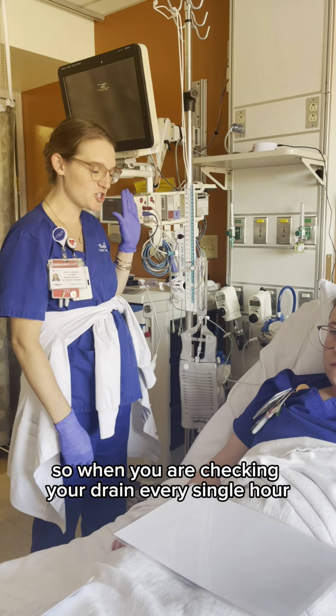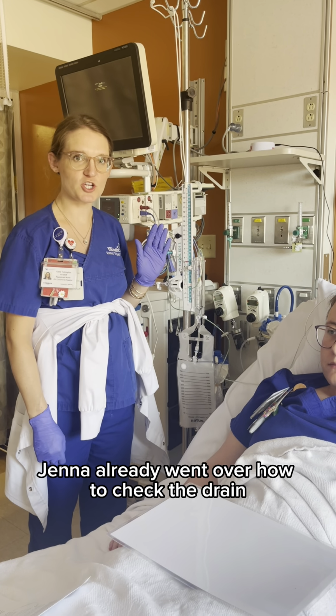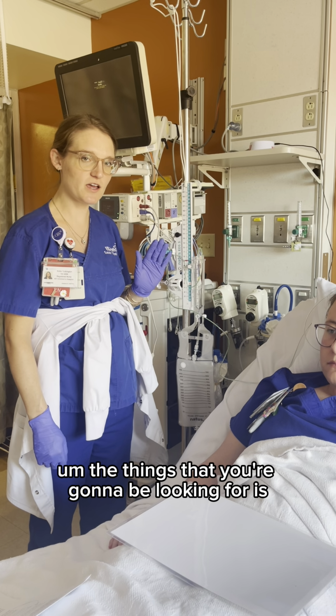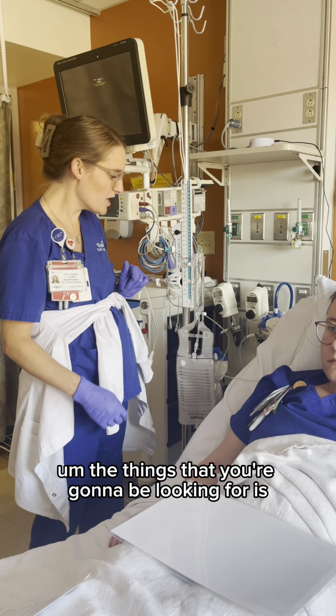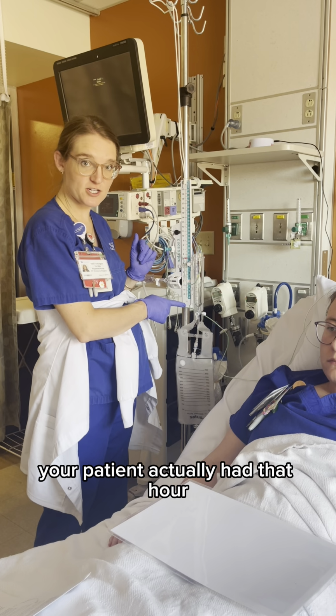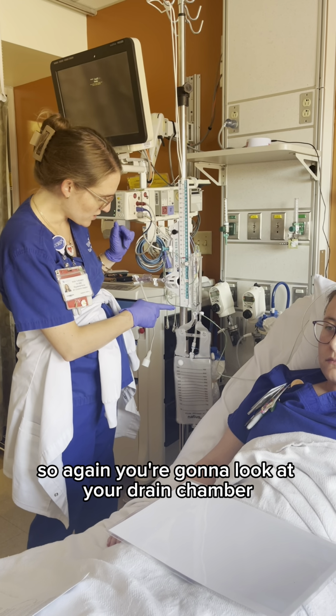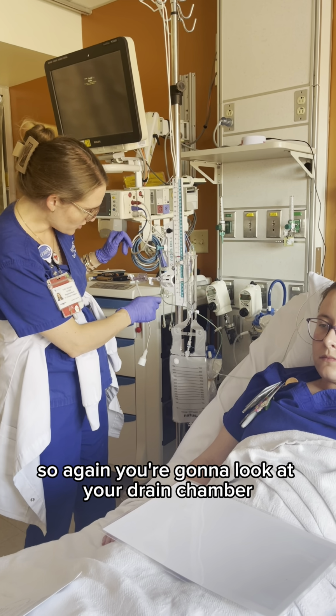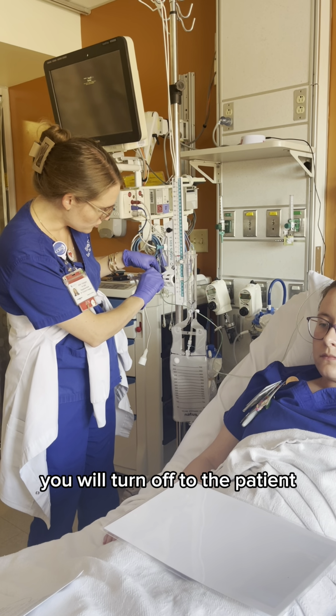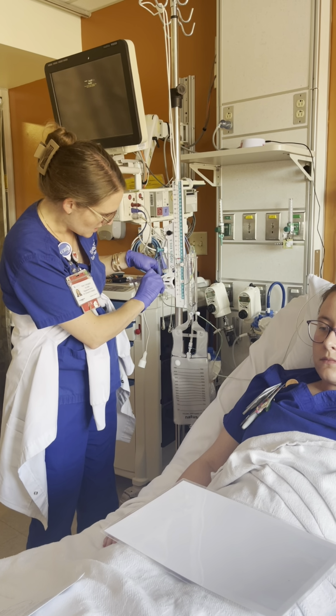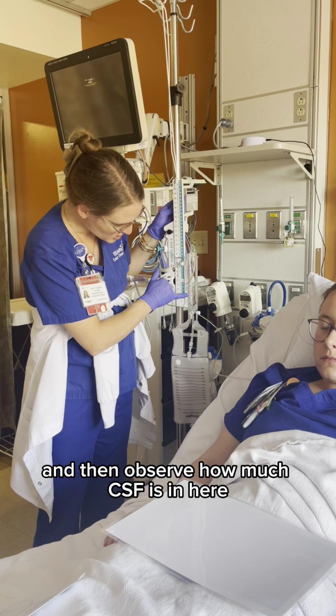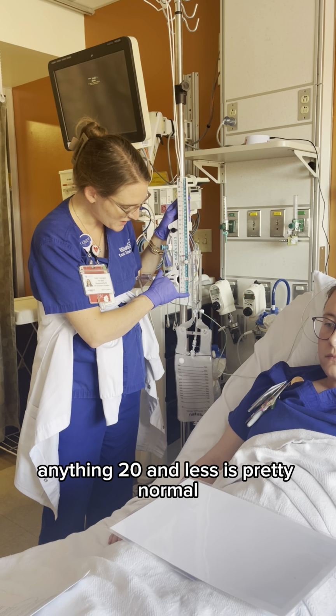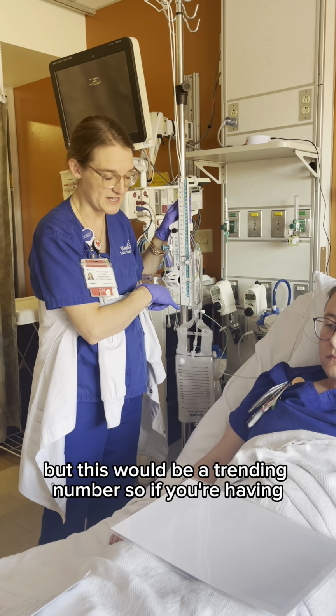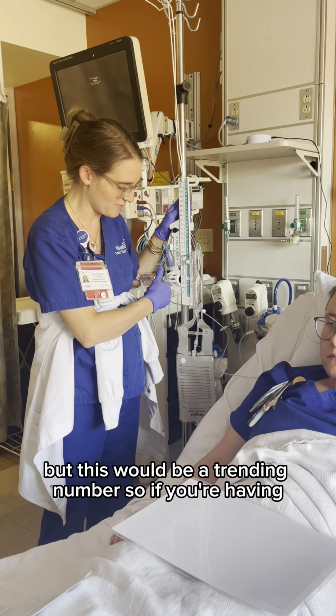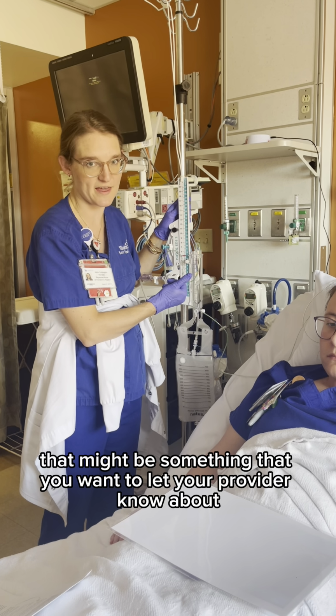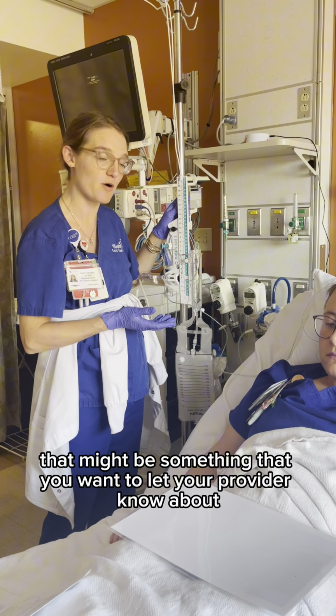So when you are checking your drain every single hour, Jenna already went over how to check the drain. The things that you're going to be looking for is you're going to look at how much output your patient actually had that hour. So again, you're going to look at your drain chamber. You will turn off to the patient and then observe how much CSF is in here. Anything 20 and less is pretty normal, but this would be a trending number. So if you're having 2 out and then all of a sudden you have 20, that might be something that you want to let your provider know about.